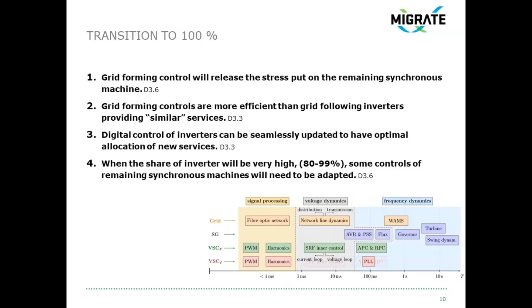As a conclusion of Work Package 3, we see that operating a system with only inverters is possible if you have at least a few grid forming inverters on the system. The grid forming function can be kind of unifying because they behave exactly the same way in small signal. You can describe with very basic requirements something that would fit the purpose and make the system stable. So we have at least one current limiting strategy that can protect any sensitive power electronic device working in grid forming mode. We think it's very good because it would avoid overcosts linked to oversizing or transient overcurrent.